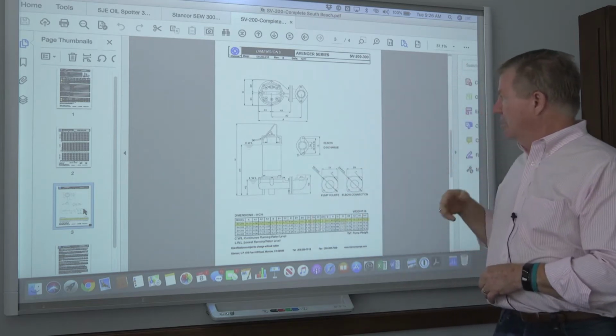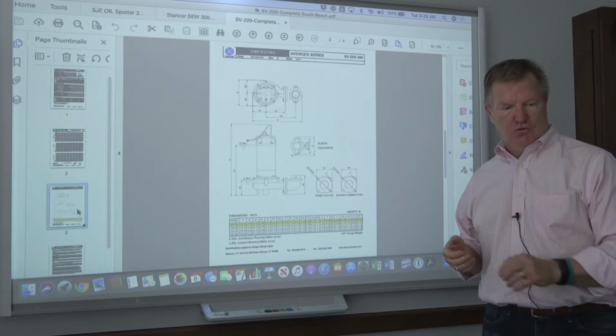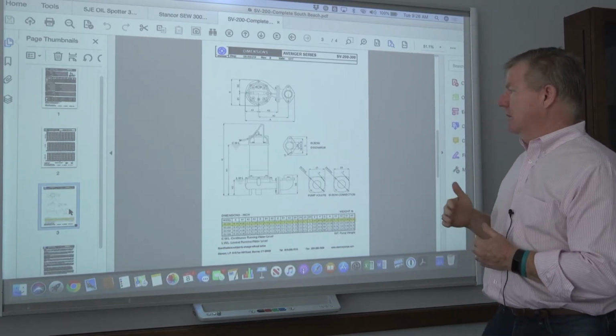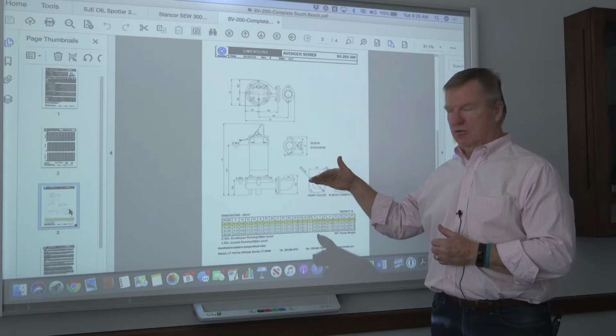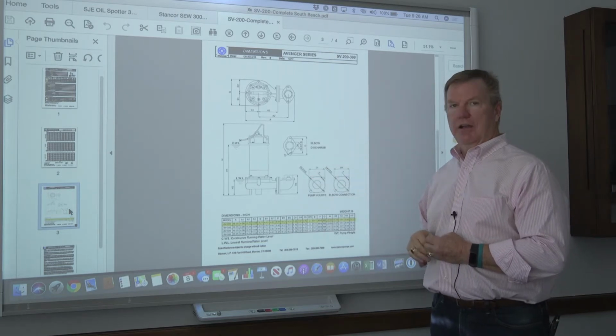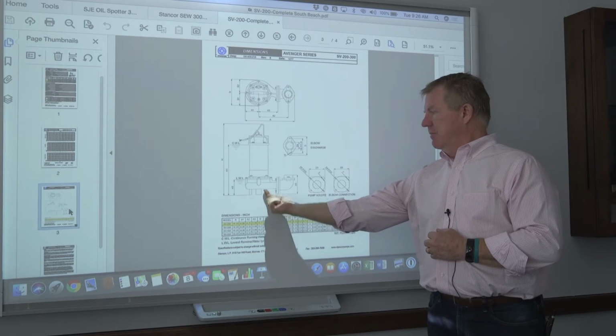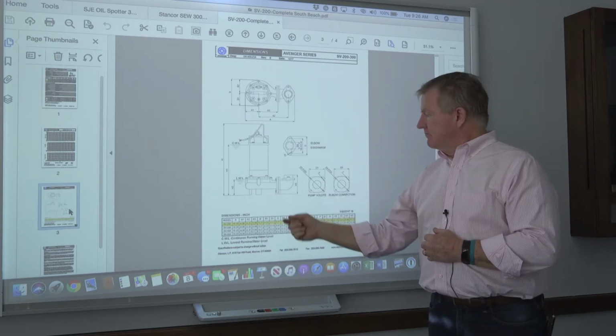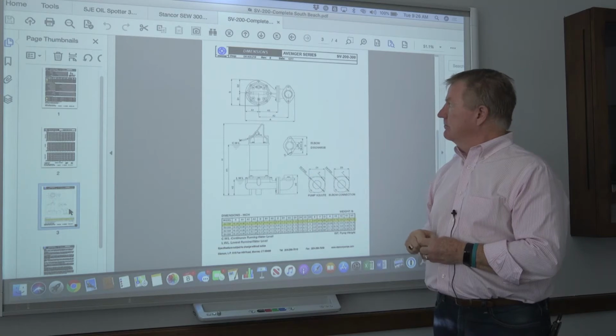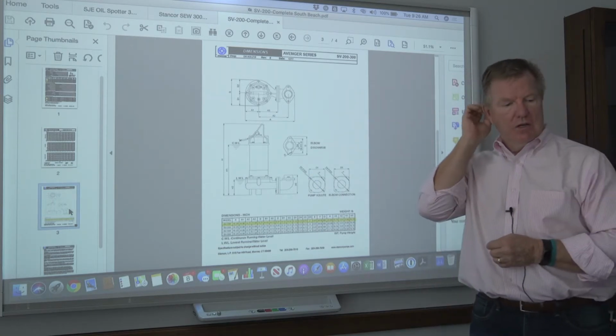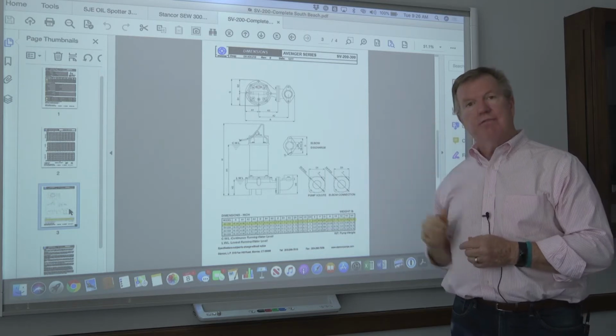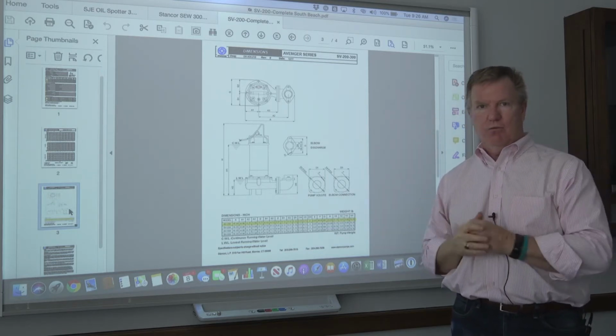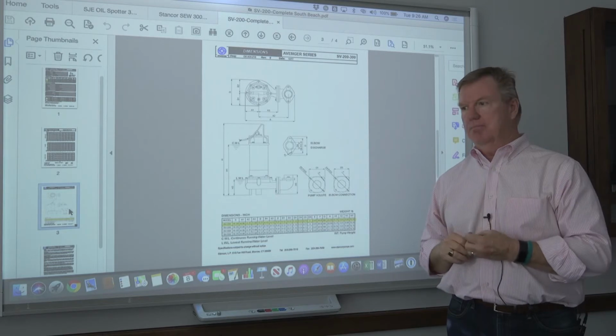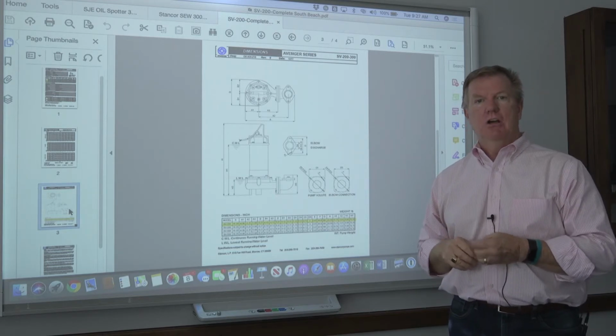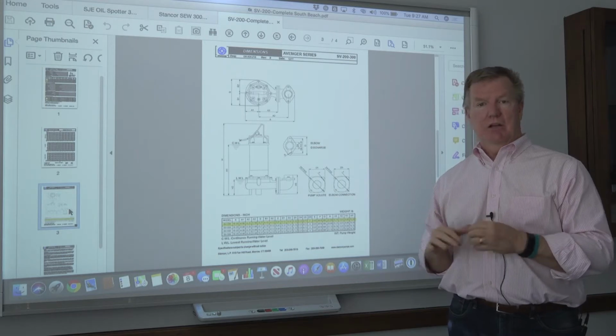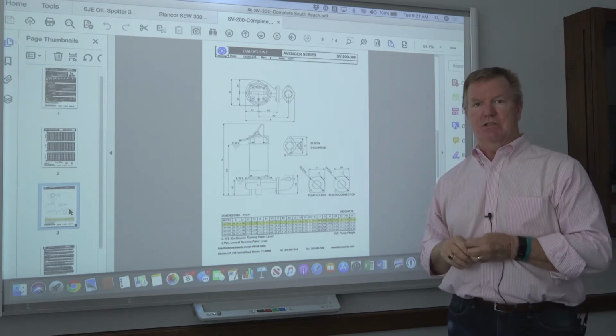Each of them is mounted with a set of controls so that when the water gets to a certain level, it automatically turns on the pump, pumps the water down, and then turns back off. The suction on the sump pumps is on the underside here, and the discharge goes out here. It's a centrifugal impeller that's in there. It's designed for sump pump service, but not for sewage or a vortex style of impeller. So it will pass small solids, but nothing big like a solid that you would see in a sewage system.